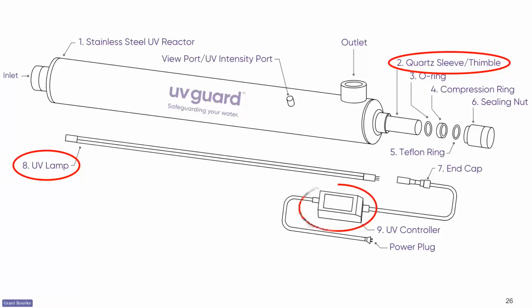There's generally a controller. It hangs on the wall. It beeps furiously if it detects that the lamp has failed. You can hook it up to the customer's burglar alarm system if they really want to get carried away. And it usually has a countdown timer on it showing how many days to go, so that the customer knows that it's time to get you around to sort out the lamp and give the quartz sleeve a bit of a clean.